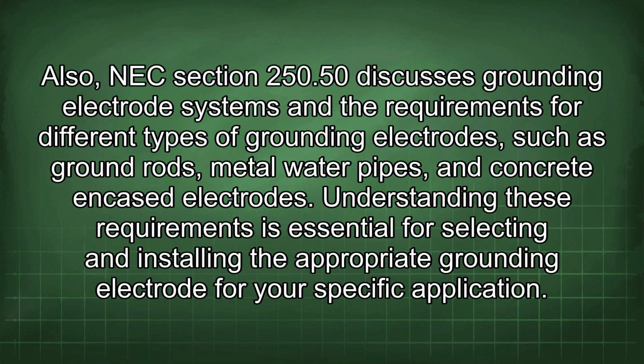Also, NEC Section 250.50 discusses grounding electrode systems and the requirements for different types of grounding electrodes, such as ground rods, metal water pipes, and concrete encased electrodes. Understanding these requirements is essential for selecting and installing the appropriate grounding electrode for your specific application.